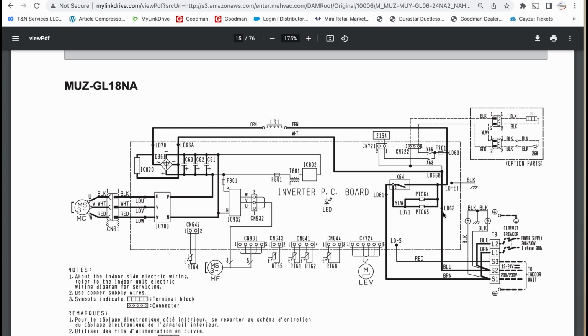So that's those 2 points on the test point diagram on the back of the board that we saw, right? So we can take voltage right here. That's going to give us our 208, 230, okay? Then we feed through, we feed up. One leg right here feeds into this one fuse, and that's F701. And what that 701 is going to do is feed over, and anything that's 208, 230 inside that unit, like your pan heaters or your reversing valve, is going to feed off that fuse 701, right?